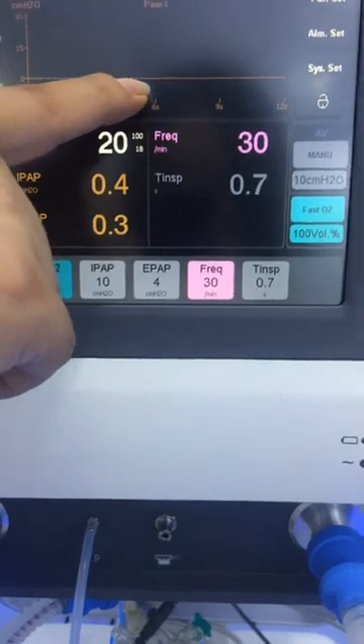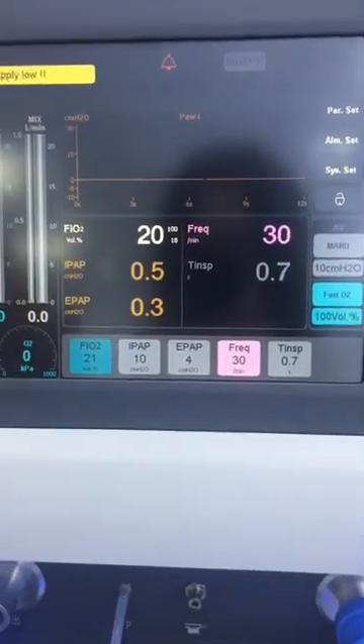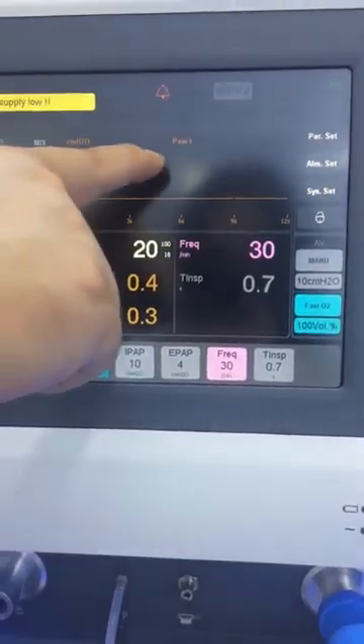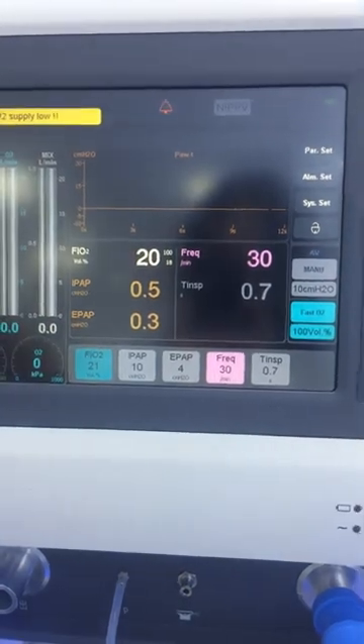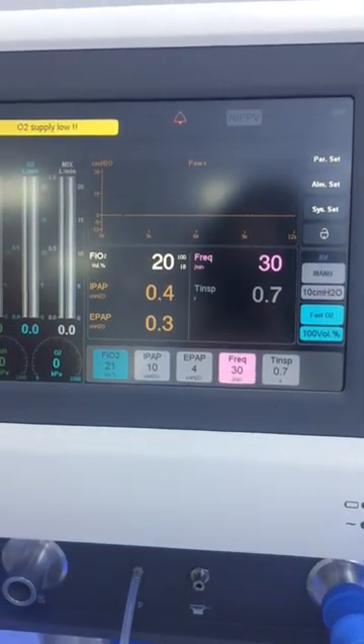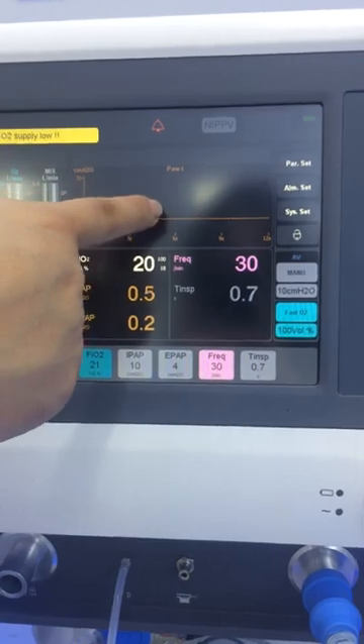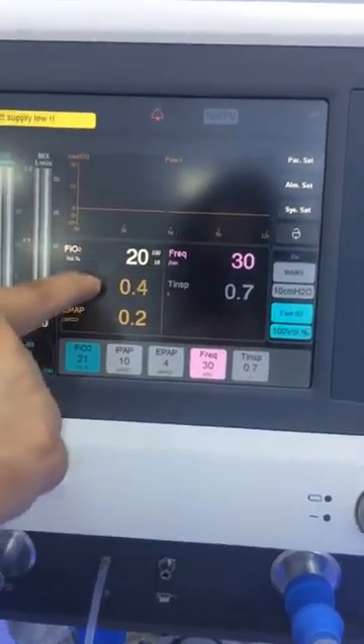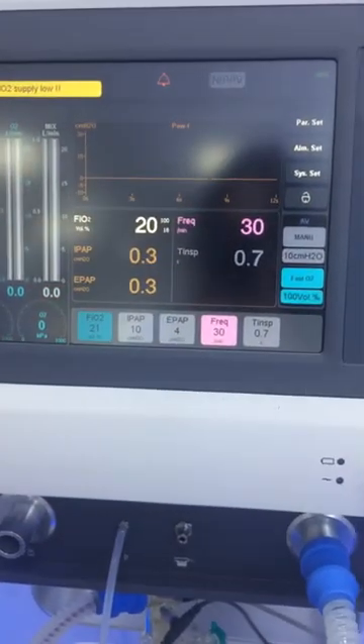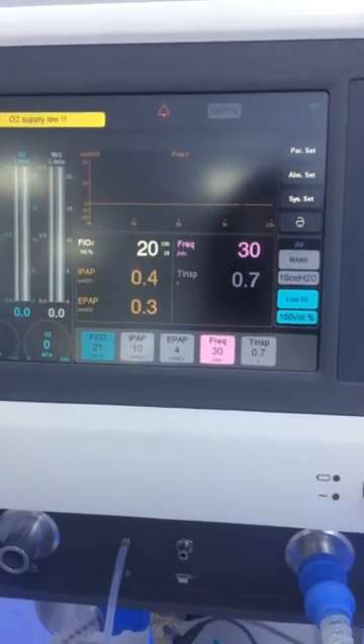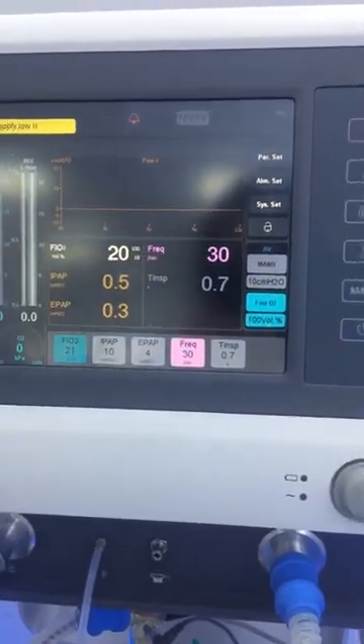So here we can check the inlet pressure for the air gas source and the oxygen gas source. Then the middle side here is the waveform, and usually we are showing the pressure-time waveform because this is the most important waveform for doctors to see the patient's situation. So we'll keep it. And then here we have some parameters to be shown, like the oxygen concentration, inspiration pressure, expiration pressure, frequency, and the inspiration time.